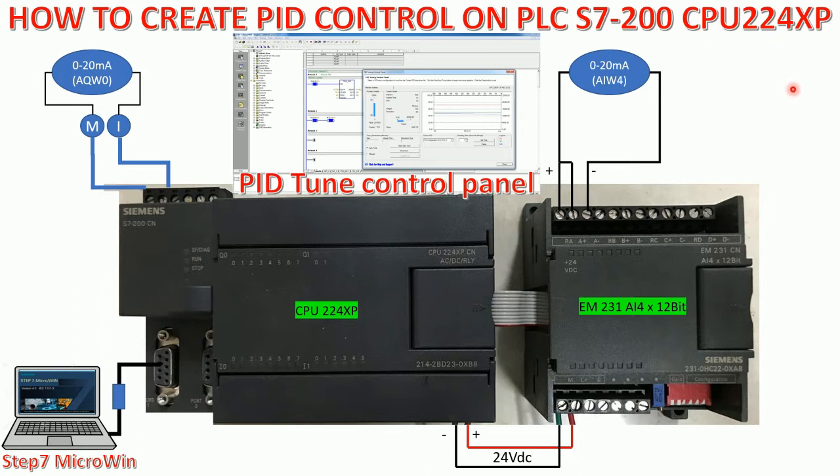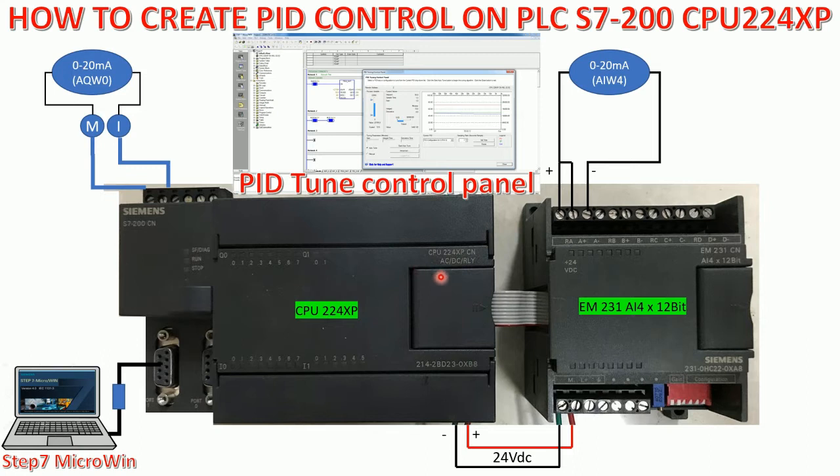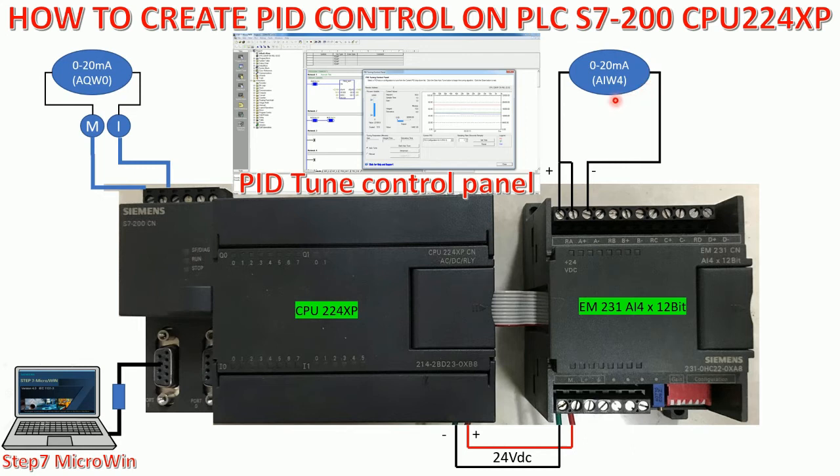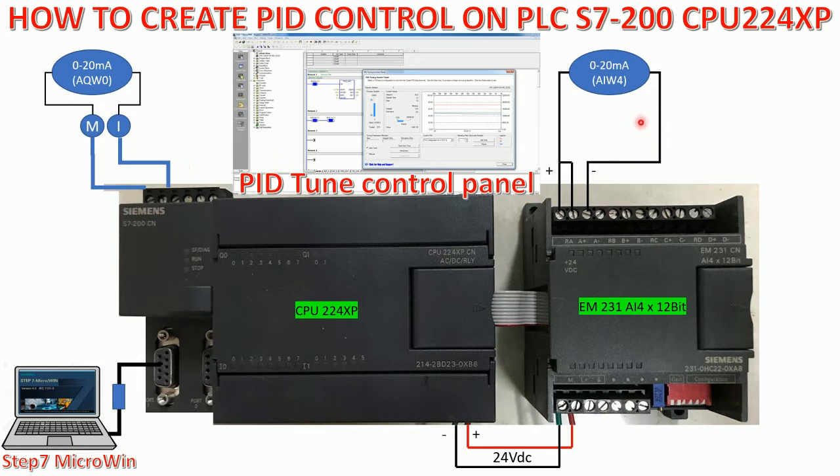And here is the PLC S7-200 CPU 224XP CN. I will connect the analog input for the extension. We already learned this in the previous video. It will start from analog input address AIW4 and go to analog output AQW0. Right now I will use the 0 to 20 milliamp because if we have the input 0 to 10 volt we can also use this terminal, but this time I will use the current 0 to 20 milliamp.